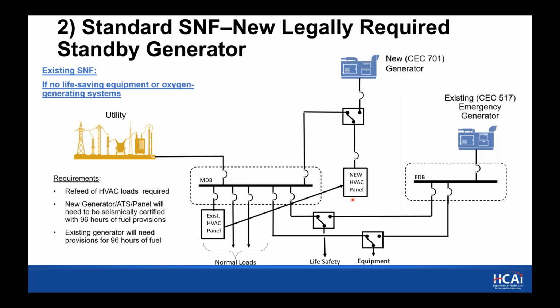The new generator transfer switch panel will need to be seismically certified, and the new generator will need to have provisions for 96 hours of fuel. In addition to that, the existing generator will need to have provision for 96 hours of fuel. So in this case, the building is intended to be occupied for 96 hours, and the life safety systems on the existing generator will need to be operational for those 96 hours.